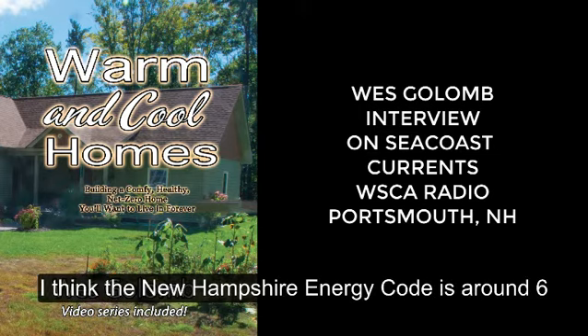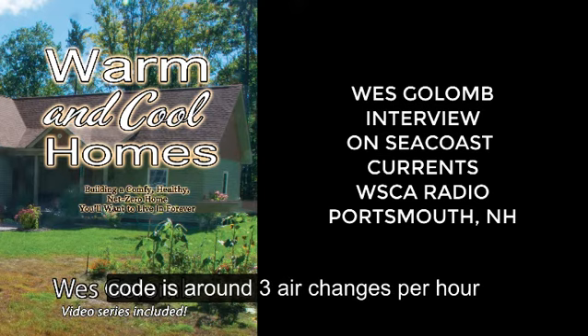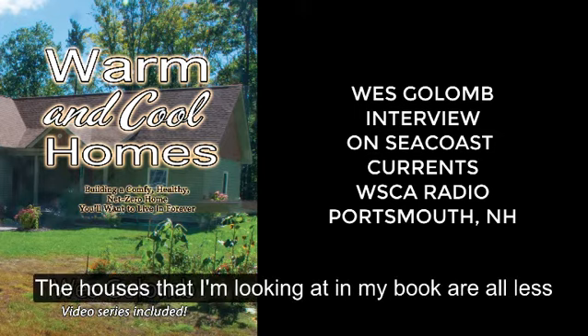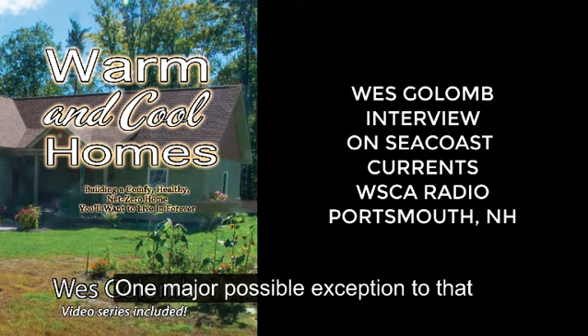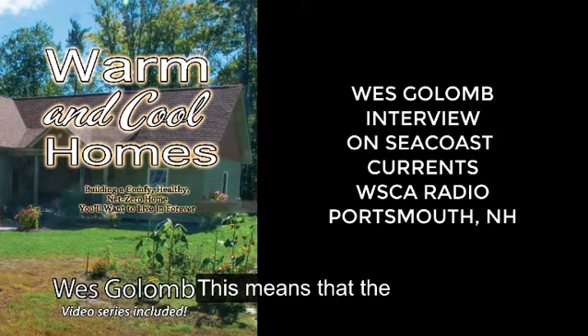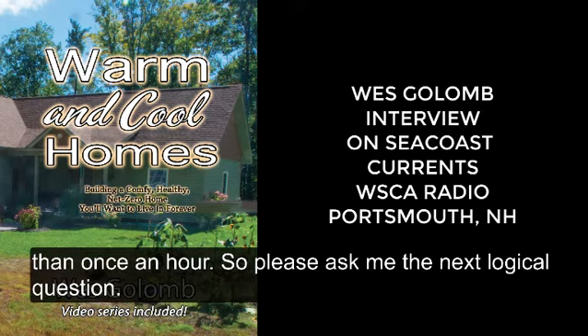I think the New Hampshire Energy Code is around 6 or 7 now, air changes per hour. The national code is around 3 air changes an hour. The houses that I'm looking at in my book are mostly all less than 1 air change per hour, with one major possible exception. So these houses are very, very tight. This means that the volume of air changes only less than once an hour.